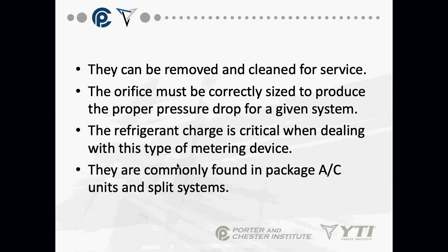Okay, it's very important they're properly sized. They're not interchangeable between different system sizes. Okay, and the charge is critical. Okay, it is a critically charged system. In other words, if the system has a leak, can you just top off the system? No. Well, you can, but it's not the right way to do it.